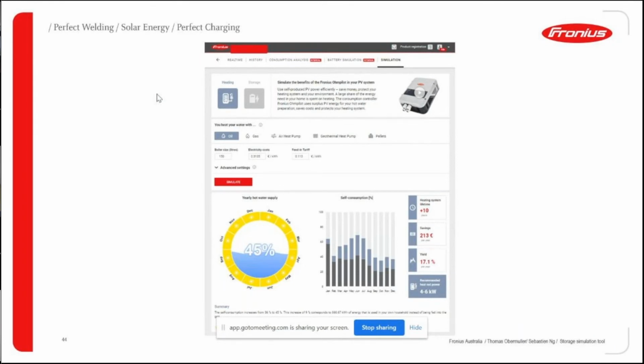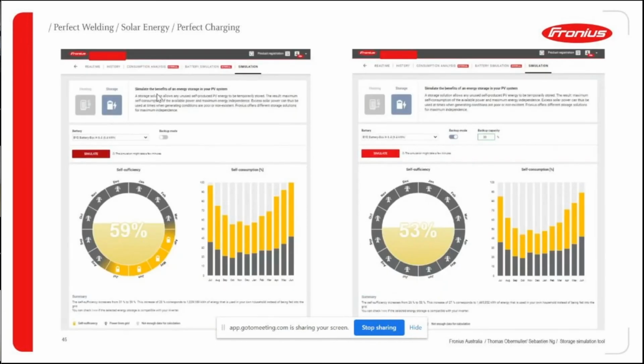Once you click on Storage, it'll bring up all the different BYD battery sizing options, and you can select different batteries, and it tells you what the self-sufficiency rate is going to be if that battery is added to the system, because it's doing calculations in the background based on the customer's consumption from the smart meter, and also their PV production.